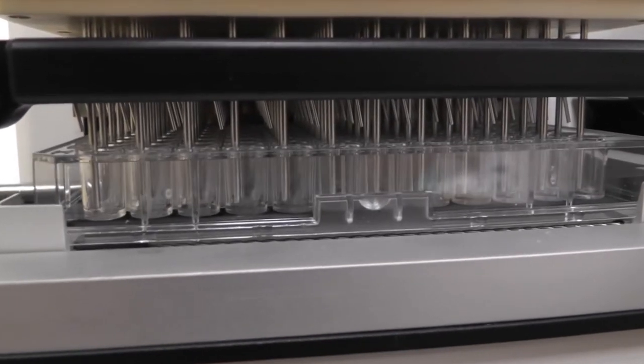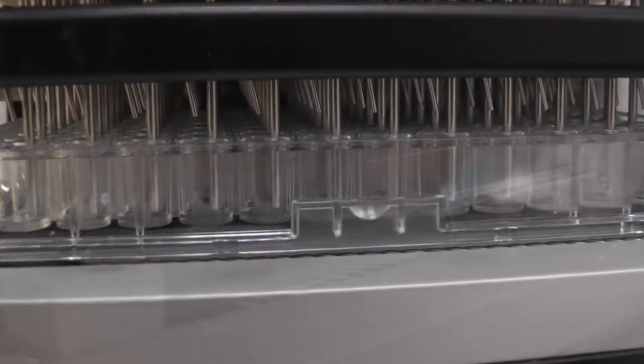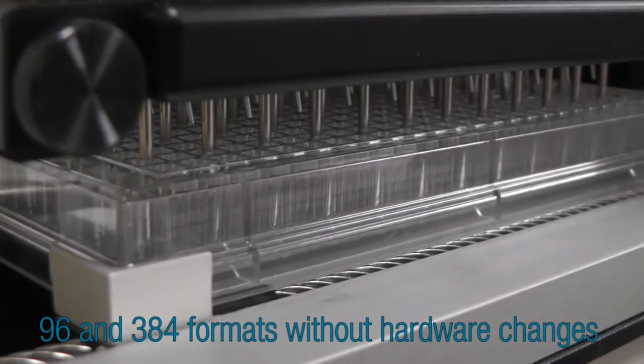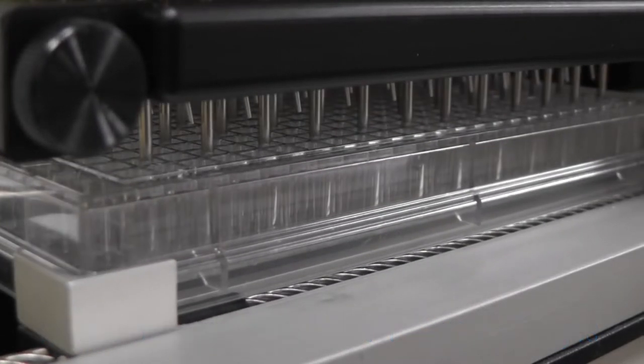The Zoom HT washer processes 96 well, 96 well strip plates and 384 well microplates with no hardware changes. Our 96 well wash head rapidly indexes to each quadrant of the 384 well format.